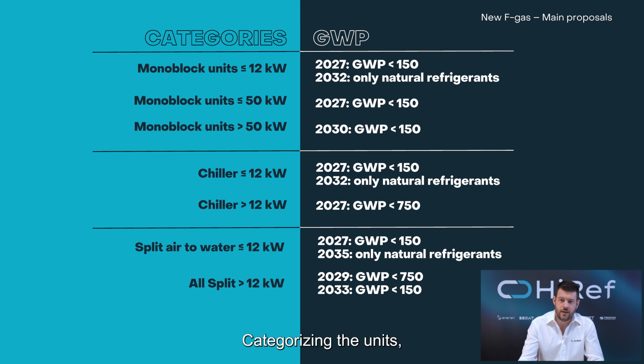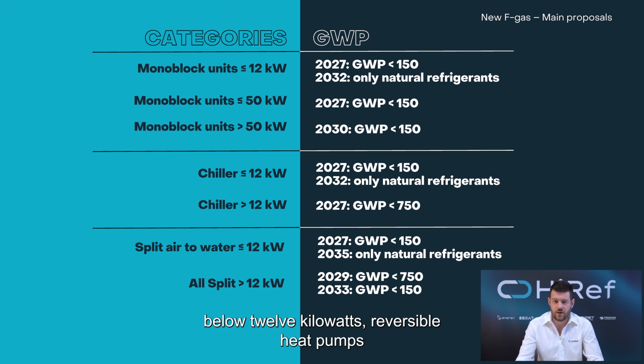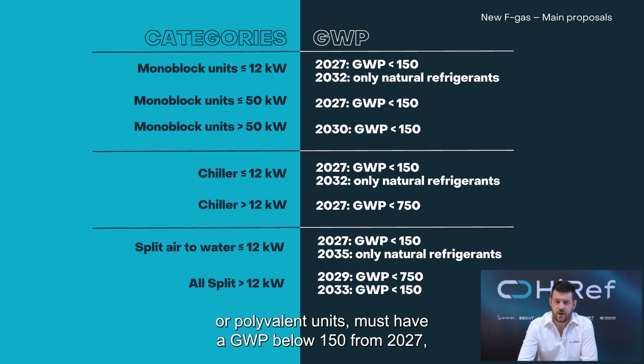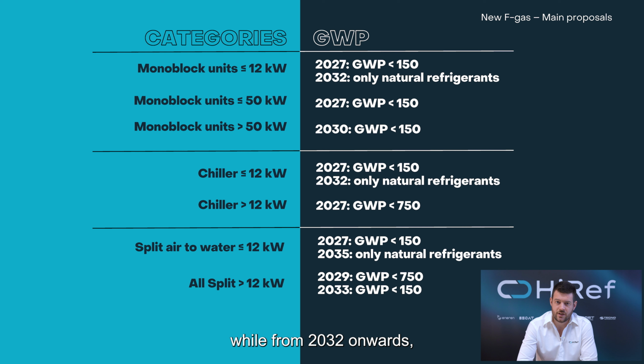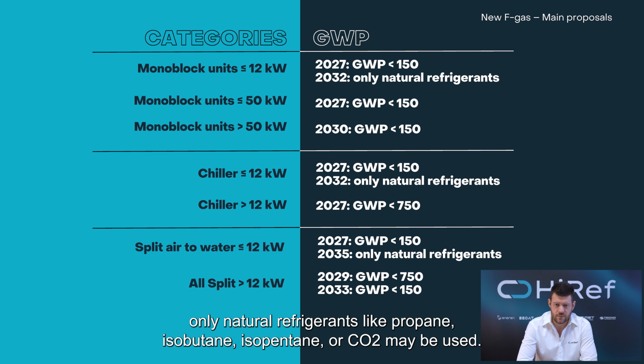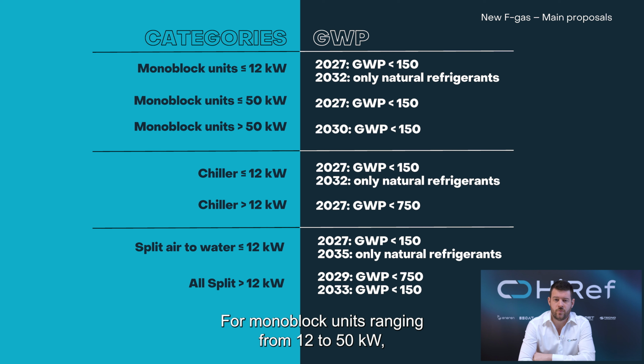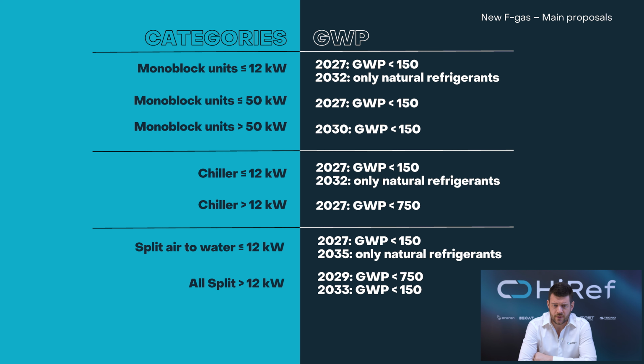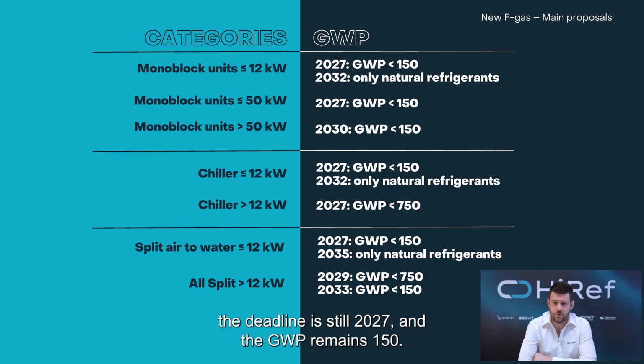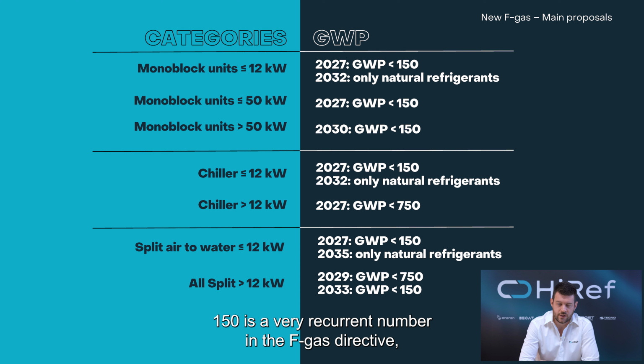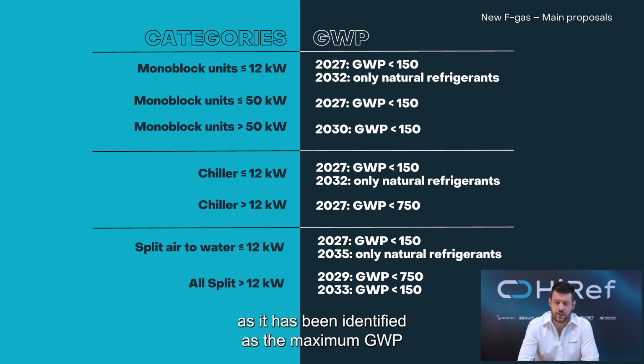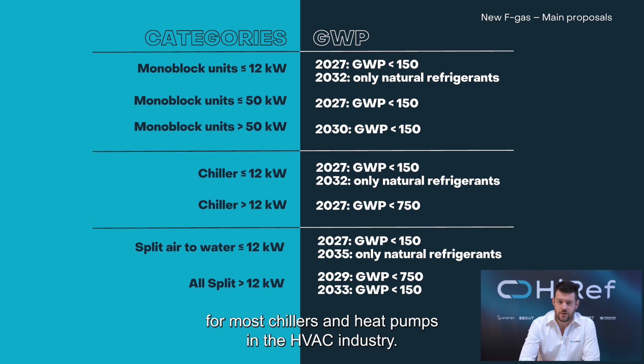Categorizing the units, we can see that monoblock units below 12 kW, reversible heat pump or polyvalent units, must have a GWP below 150 from 2027, while from 2032 onwards only natural refrigerants like propane, isobutane, isopentane or CO2 may be used. For monoblock units ranging from 12 to 50 kW, the deadline is still 2027 and the GWP remains 150. 150 is a very recurring number in the F-gas regulation, as it has been identified as the maximum GWP of the refrigerant permitted for most chillers and heat pumps in the HVAC industry.